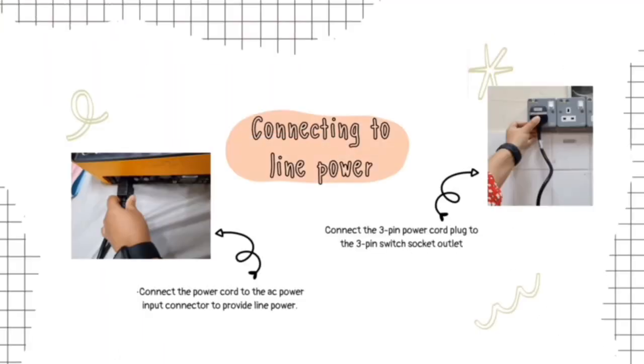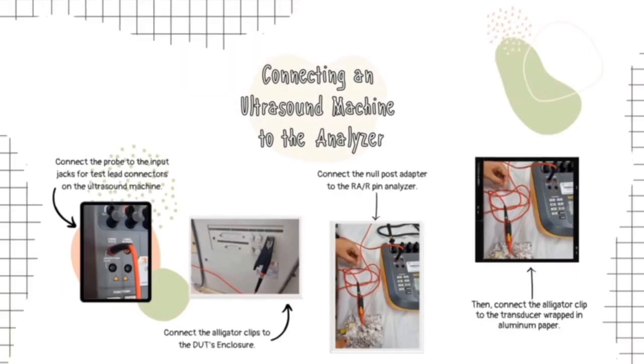First of all, we must connect the line power. First, we must connect the power cord to the AC power input connector to provide the line power. And then, put the 3-pin power cord plug into the 3-pin switch socket outlet. The next step is connecting the ultrasound machine to the analyzer.